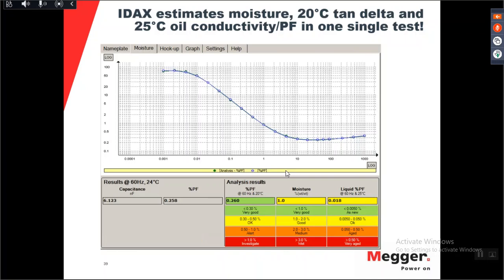Okay, another question. Should we do trending, and is there any guidance on when to test again after a particular high moisture finding? The moisture ingress is very slow. You can do trending, but I would probably go out and check the transformer and get the condition, and then I would do it every 5 years. That would be my choice, if I would write the standards. There is no need for doing it every single year.